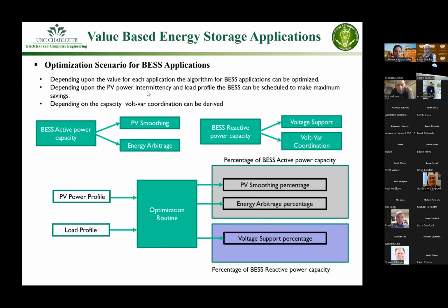Volt-var coordination and voltage support, when you look at it, may sound the same or similar, but they're two different functionalities. Volt-var coordination is with respect to the legacy devices, for example the voltage regulator, and is basically VAR support. Voltage support is based on what is there on the voltage profile. So there are two different functions that you can have from the reactive power. Those two functions have a few other attributes associated with them, depending upon the size of the battery energy storage, the distributed nature of the battery energy storage, and so forth. I'm not going into that detail, but I just wanted to mention there are two different groups or buckets.